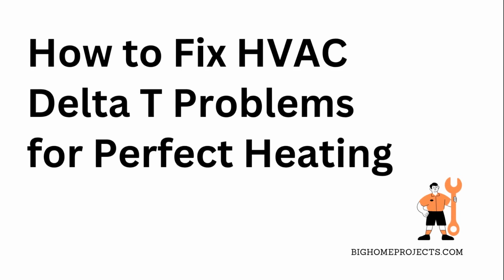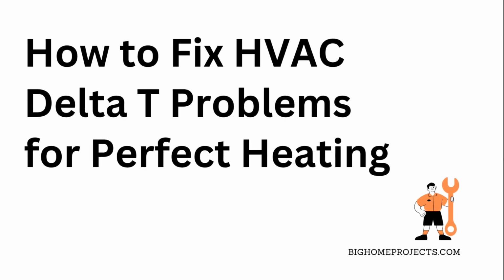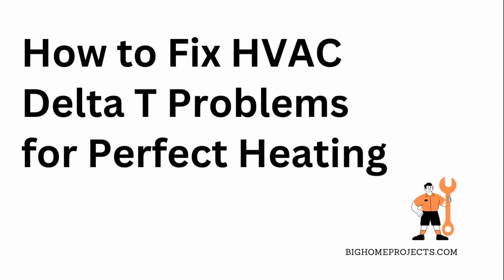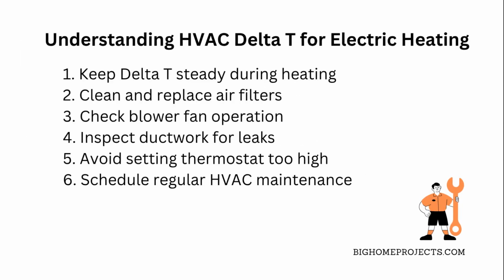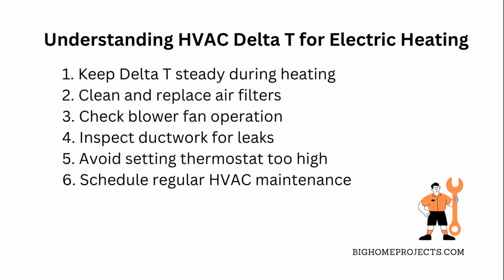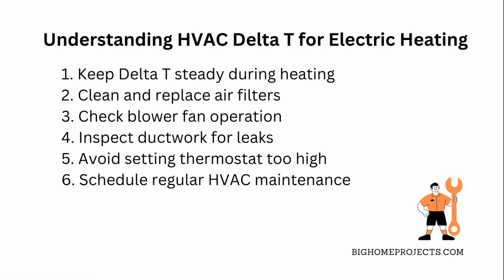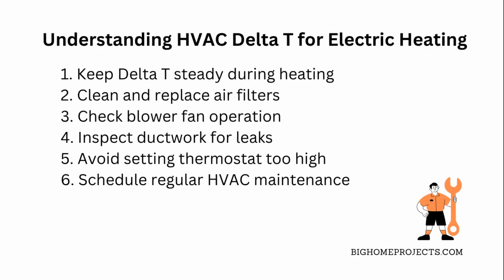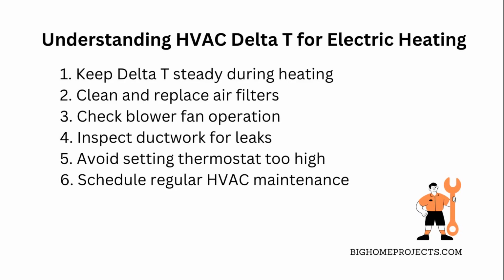Understanding HVAC Delta T is key to keeping your electric strip heating running smooth and your home comfy without wasting energy. So, Delta T basically means the difference between the air temperature going into your heater and the air coming out. When your electric strip heat is on, you want that Delta T to stay pretty steady. If it starts rising, that's a red flag. That usually means your airflow is low or something is blocking the ducts.